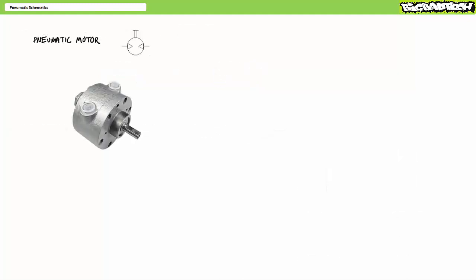Speaking of rotation, another common actuator you may encounter in pneumatic systems are pneumatic motors, which are essentially the opposite of compressors. And the schematic symbol tells us this quite succinctly. A compressor converts rotational mechanical power to fluid power. In contrast, a pneumatic motor converts pneumatic power to rotational mechanical power. Note the arrows of a pneumatic motor pointing inwards, indicating the pneumatic motor consumes pneumatic power, whereas the compressor provides it. Bidirectional pneumatic motors have two inward pointing arrows, whereas unidirectional pneumatic motors have a single inward pointing arrow.